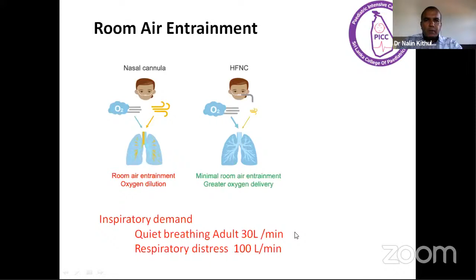For example, in quiet breathing in an adult, they need about 30 liters per minute. So if you are not supplying these 30 liters per minute from the oxygen delivery device, invariably part of it is from room air. In respiratory distress in an adult, this can go up to 100 liters per minute. You can see even the maximum amount of high flow nasal prongs cannot supply this. So that is why it is important to use the maximum flow rate in high flow.